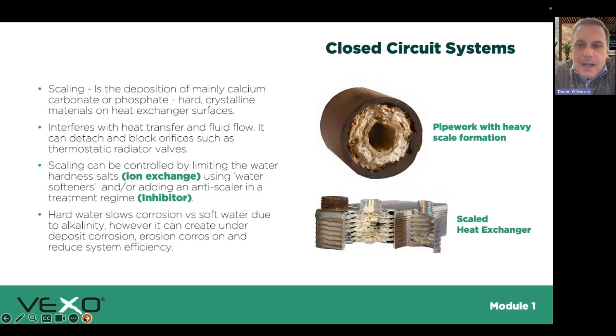Ironically, scale can actually act as a bit of an inhibitor - it somewhat passivates the surface - but unfortunately it opens up other problems. One is energy loss, as scale builds up at the point of heat exchange. That scale will also break off, almost powdering, and microscopically it becomes very abrasive to the pipework runs and other equipment on the system.